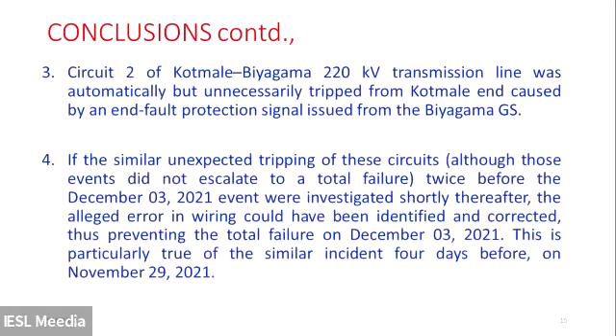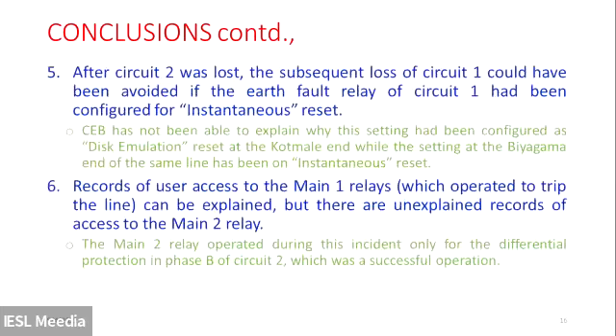and when we looked into the history, we got a similar case where this end-fault protection operation on the 21st of May 2021 in the same line, and also on the 29th November, a similar incident had taken place. Now, our observation is that if this had been investigated previously when the incident took place, probably this could have been avoided if it happened due to any wiring error or some other problem in the maintenance. So which could have been avoided, but unfortunately it did not happen.